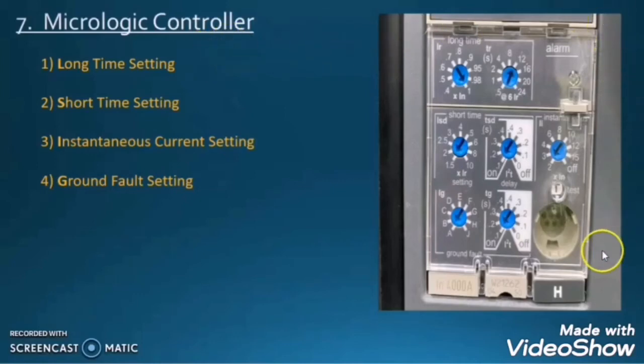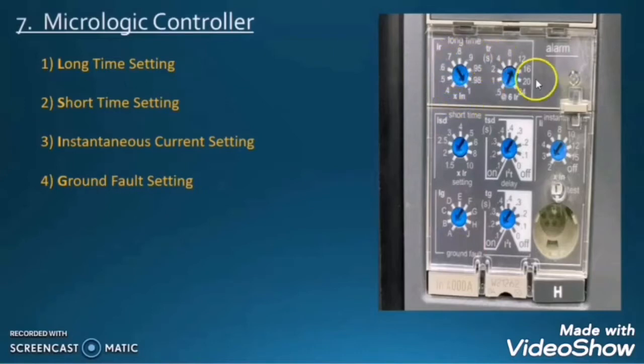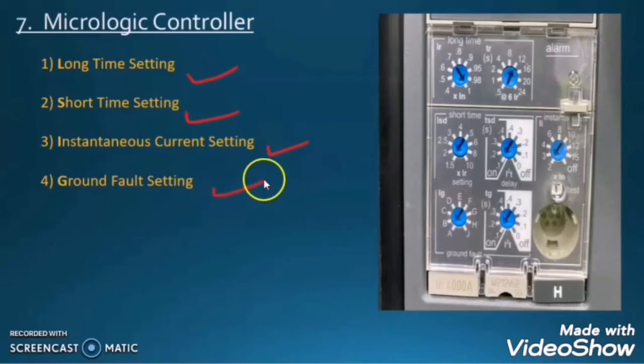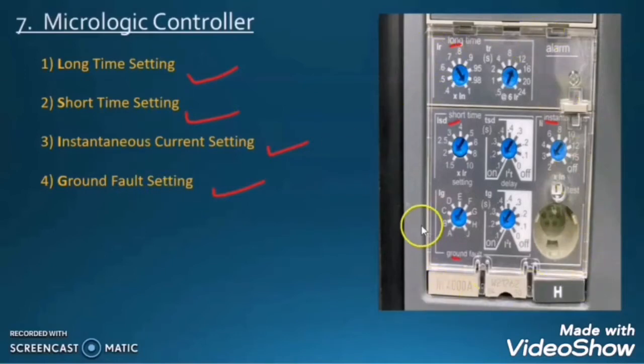The next detail available on the air circuit breaker is a micrologic controller. These micrologic controller dials give us the facility to set our air circuit breaker as per the load requirement or as per the load characteristic which is connected on that ACB. There are total four settings on a micrologic controller: long time setting, short time setting, instantaneous current setting, and ground fault setting. This is a very important part of this video.